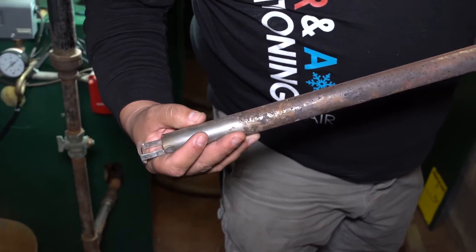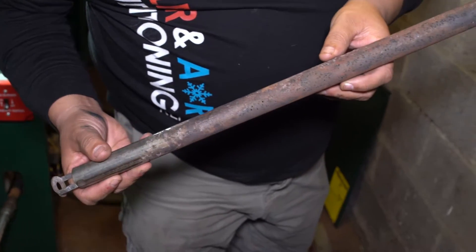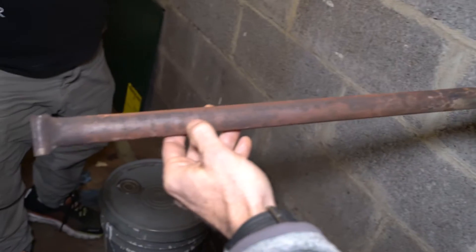So now gas is not necessarily just coming cleanly here — this is all kicked up and burnt out. He cleaned all this by hand; he was going in there with a small screwdriver. But all this pitting — yes, that's what caused it.